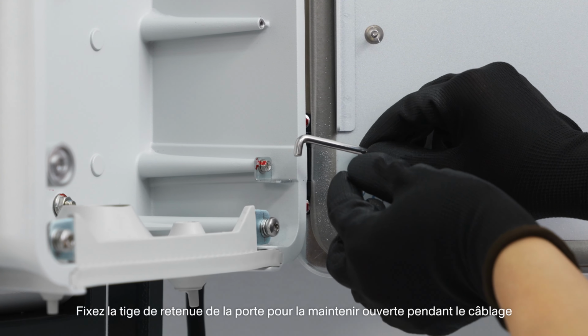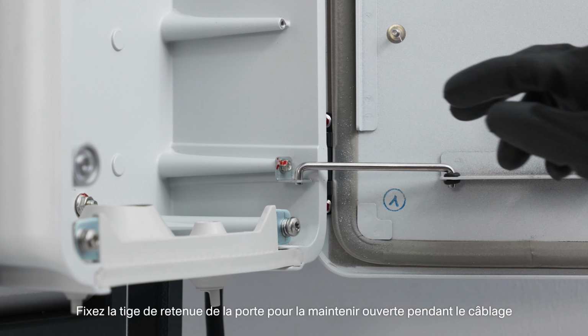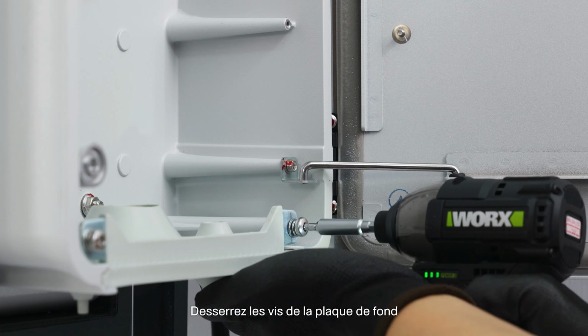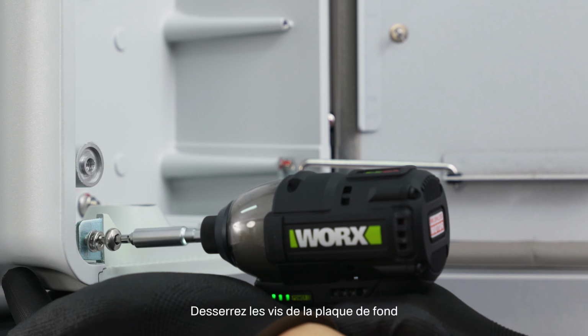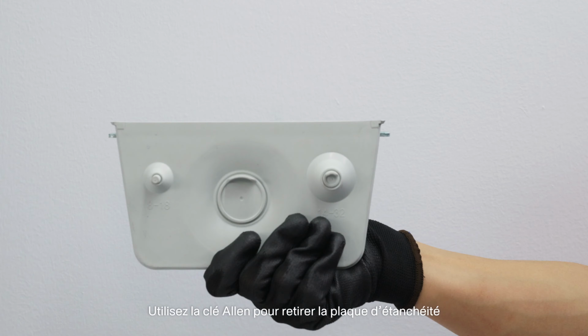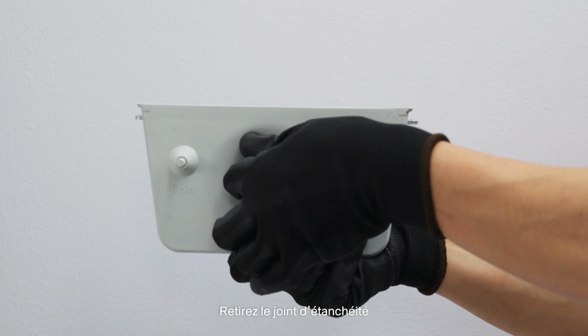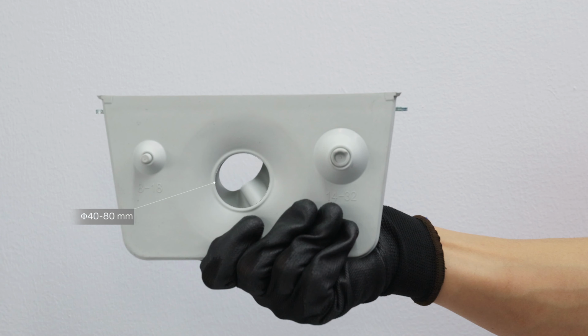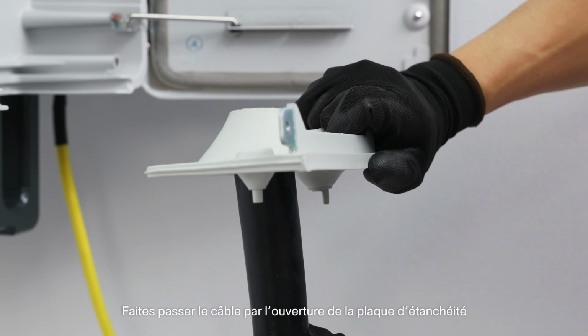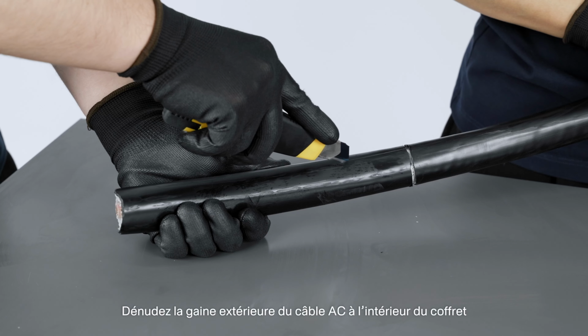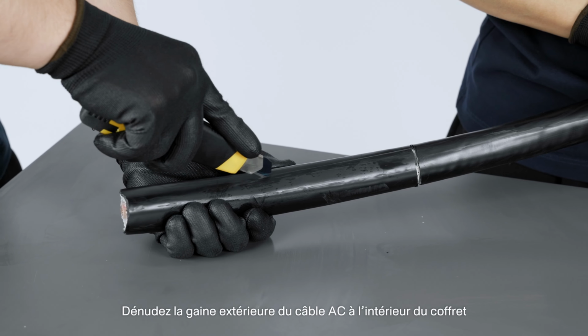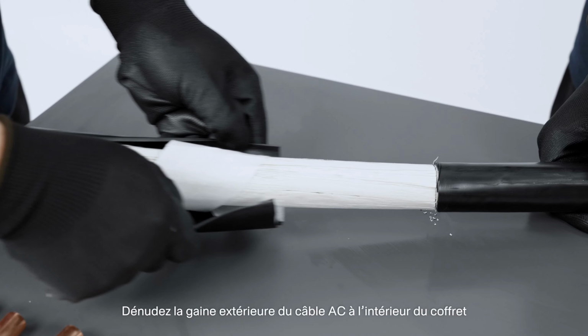Secure the door restrictor rod to keep the door open during wiring. Loosen the screws on the bottom sealing plate using the Allen wrench and take the sealing plate out. Tear off the seal. Lead the cable through the opening on the sealing plate. Strip the external protective layer of the AC cable inside the junction box.